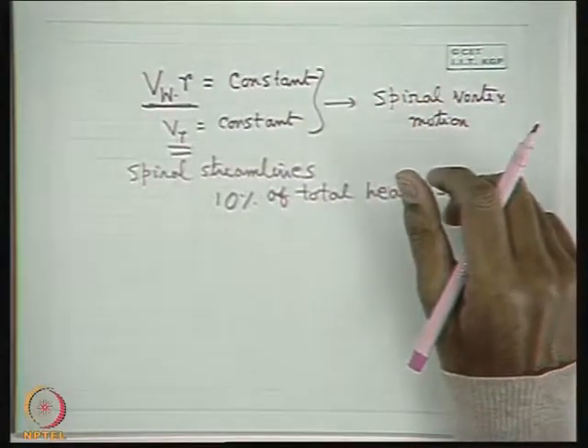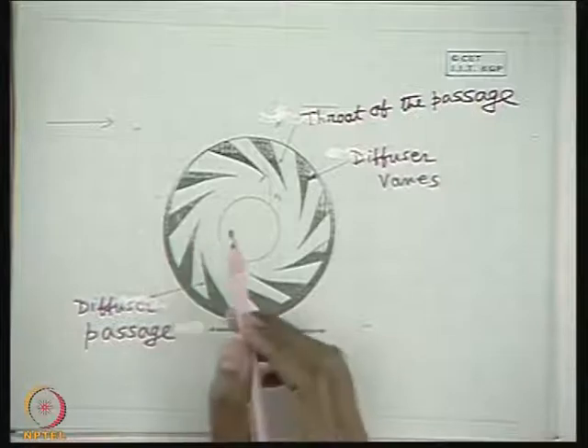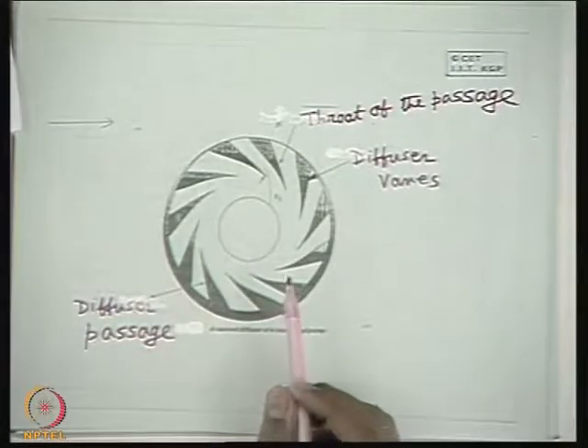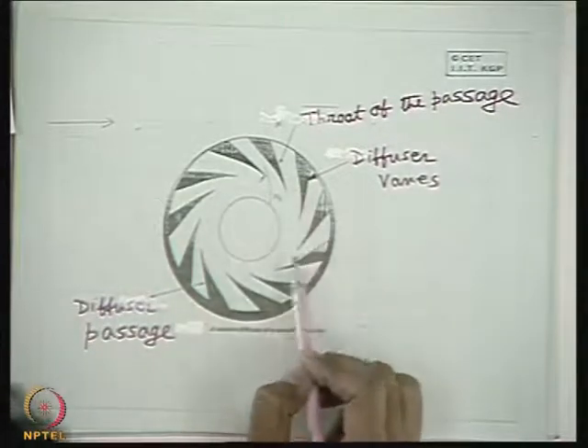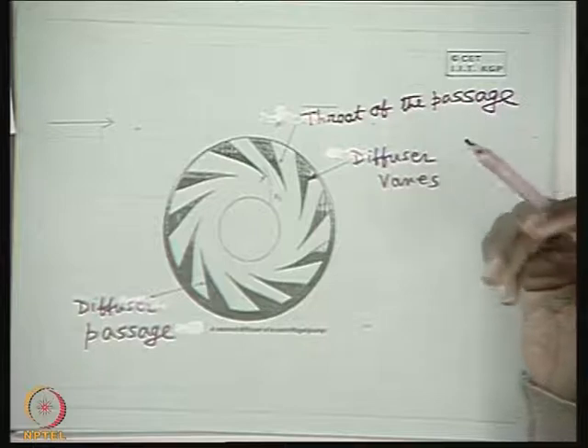Now we come to the vane diffuser. A set of static vanes act as the vane diffuser. These are provided when a shorter length of pump is required to deliver the required pressure — that is, when the rise in pressure from the impeller outlet is needed over a shorter length. The diffuser vanes act in addition to the volute casing in converting kinetic energy into pressure energy, so that we can get higher pressure at the pump outlet.